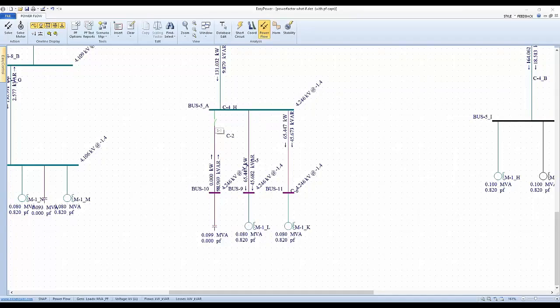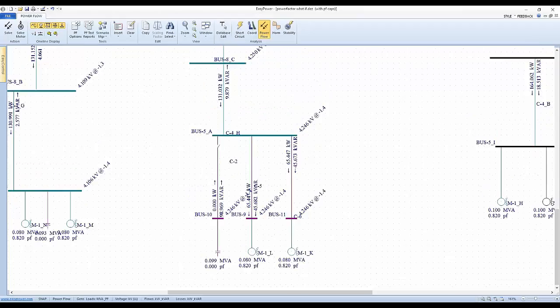If I open up this switch, you can see it takes our capacitive draw back to the utility, back to the 90 kVAR, but we haven't changed the draw by the motors.